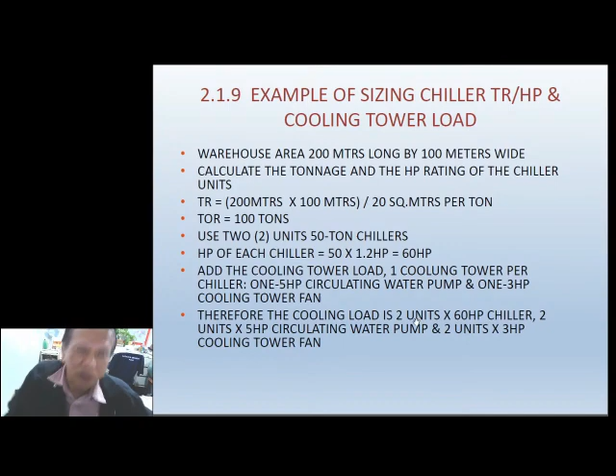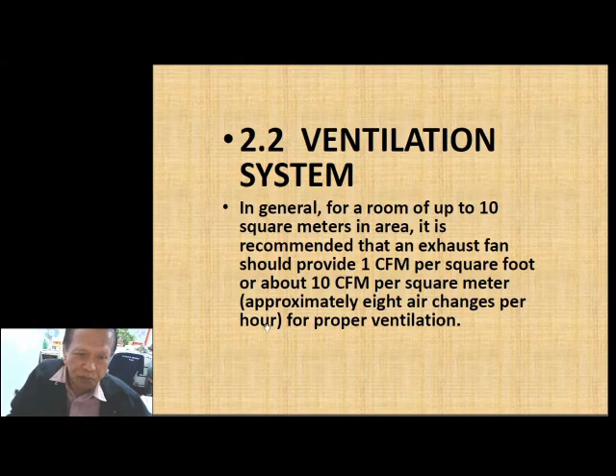In ventilation in general, for a room of something like 10 square meters in area, it is recommended that an exhaust fan should be provided at 1 cubic feet per minute per square foot, no? That's American standards, from ASHRAE. Or about equivalent to 10 CFM per square meter. Kaya kung binasa mo siya sa area, what is the length and the width, makakakuha ka ng CFM. Kasi 10 CFM per square meter or 1 CFM per square foot. Okay, this is approximately 8 air changes, or exchanges. In other words, papasok yung hangin, lalabas, pasok yung hangin, lalabas. Okay? So, to make sure that yung loob ng kwarto mo, fresh air yung nandun. So, 8 air changes per hour. Wow, matindi yun, ha? Mabilis, di ba?